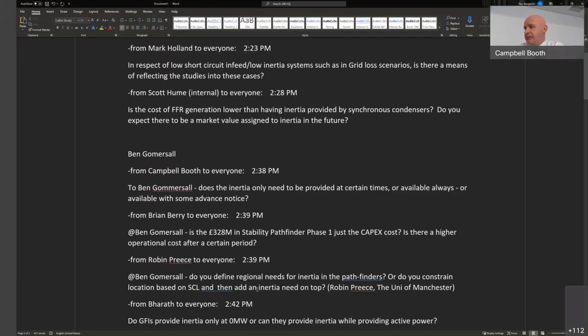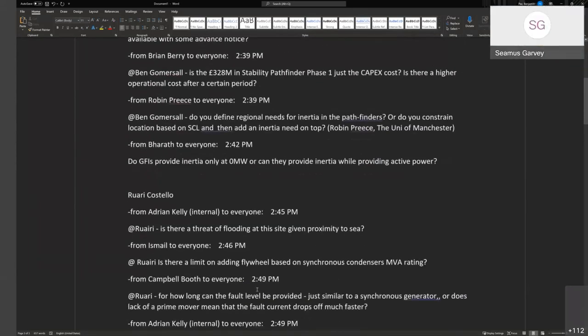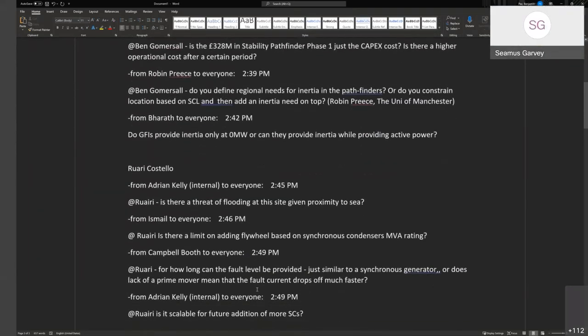I believe your instinct is exactly right, that inertia is all about controlling rate of change of frequency, and it will reduce the rate of change of frequency, whether that's upwards or downwards. Yeah. Can I add to that? From a system perspective, that's not necessarily always a bad thing, because the point of inertia is to slow everything down, to dampen it out. Moving back towards nominal quickly can be bad, because you can then get overshoots. So we may often see a low frequency event followed by a high frequency event. So it's not necessarily a bad thing that it's dampening everything down on the way up too.